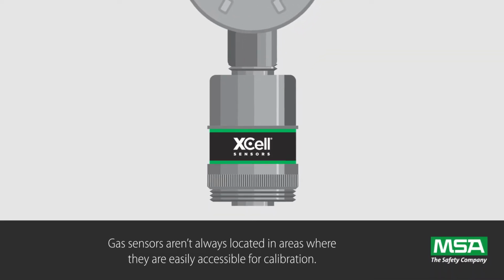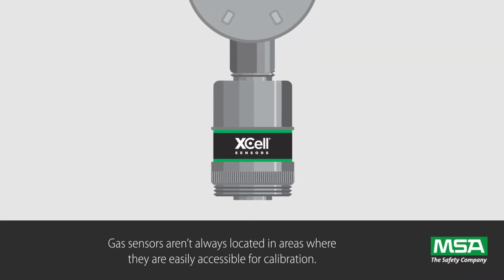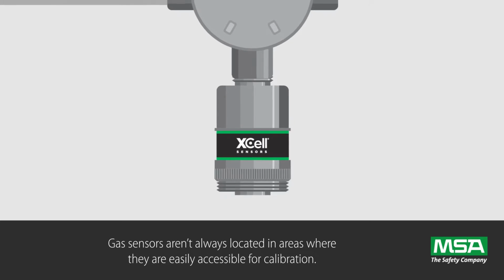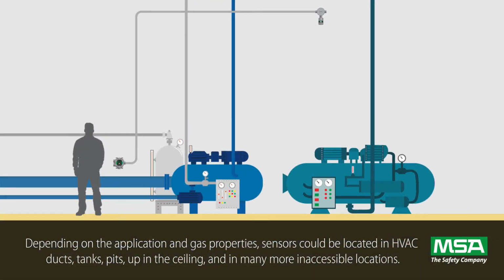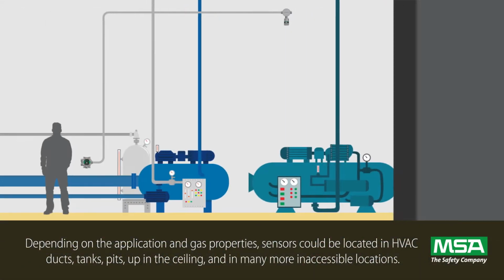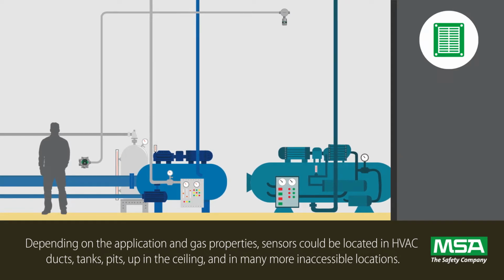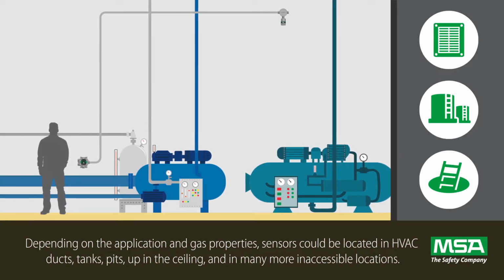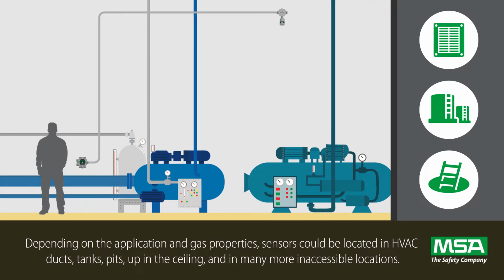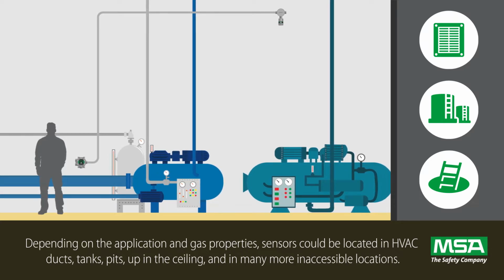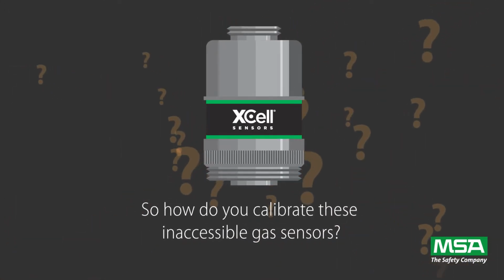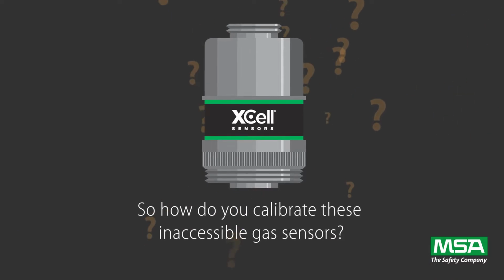Gas sensors aren't always located in areas where they are easily accessible for calibration. Depending on the application and gas properties, sensors could be located in HVAC ducts, tanks, pits, up in the ceiling, and in many more inaccessible locations. So how do you calibrate these inaccessible gas sensors?